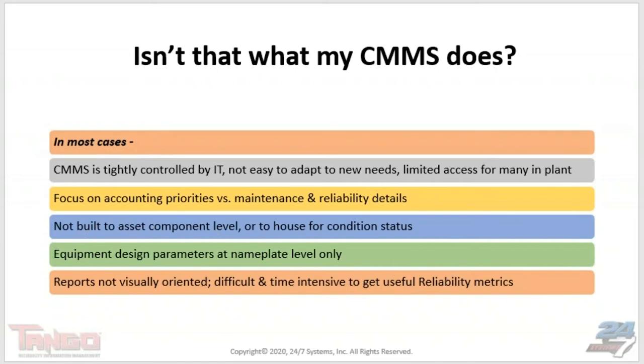One other primary issue is that many CMMS or EAM systems don't build their location hierarchy down to an asset component level — they stop at a machine train or system level. In reality, reliability occurs at knowing what's happened with each component — each repairable asset like a motor, pump, gearbox, or transformer. In most cases they're lucky to even have nameplate information, much less bearing details like drive-end versus non-drive-end, which would be very helpful to vibration analysis technicians.